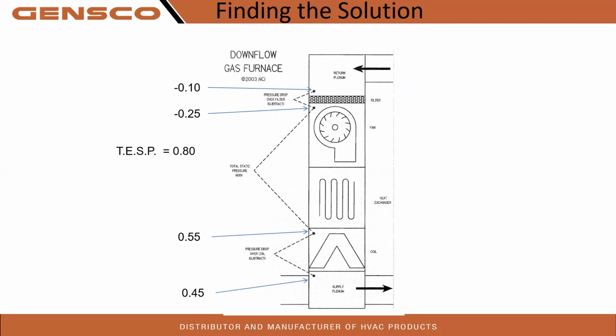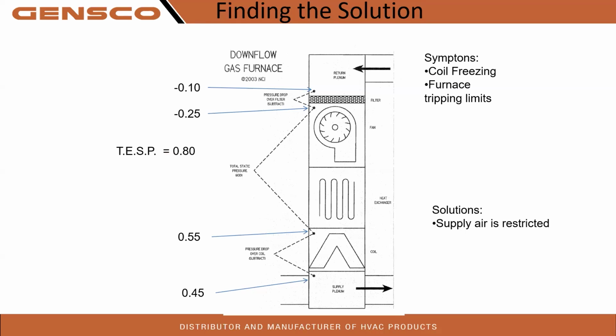All right, so here's another scenario. Total external static pressure of 0.8, 0.25. Looks like our filter's good. We got a high supply. Again, showing the same symptoms but our issue is in a different spot. Supply air is restricted.